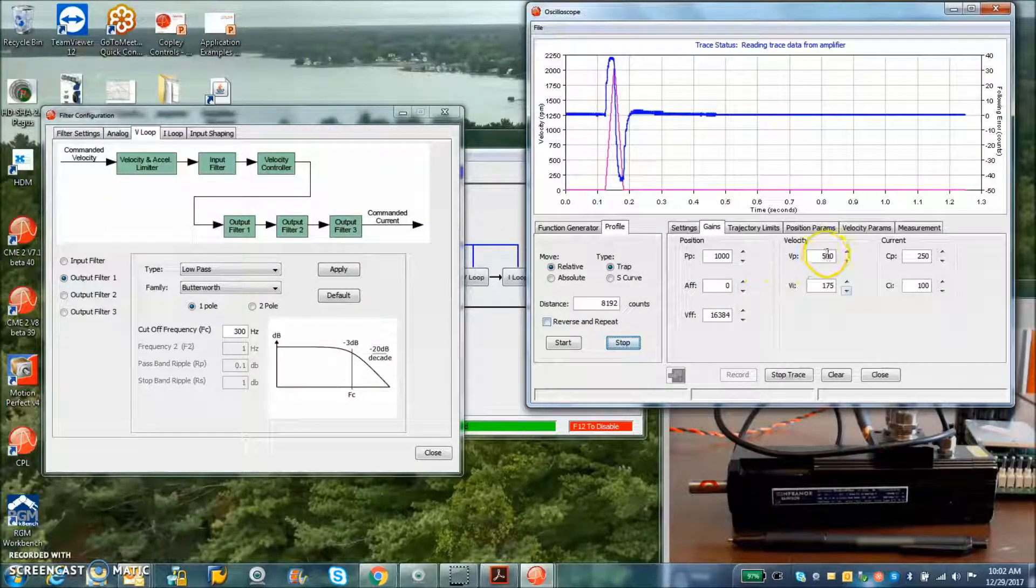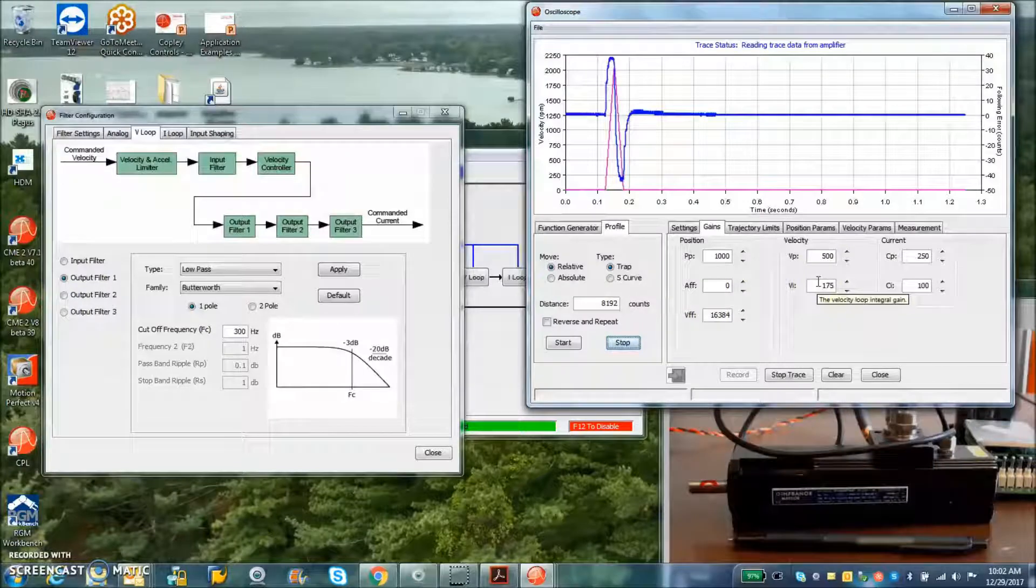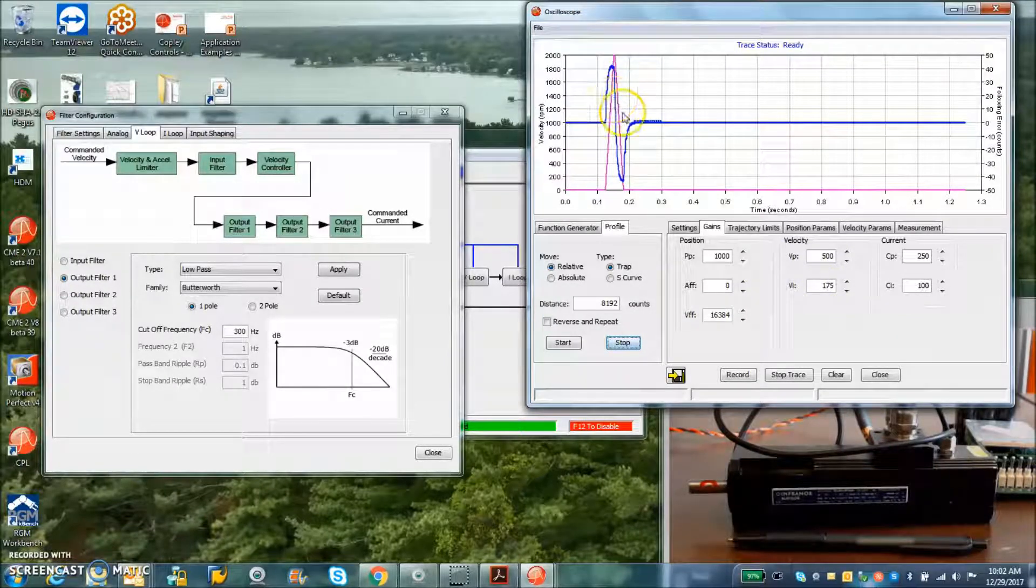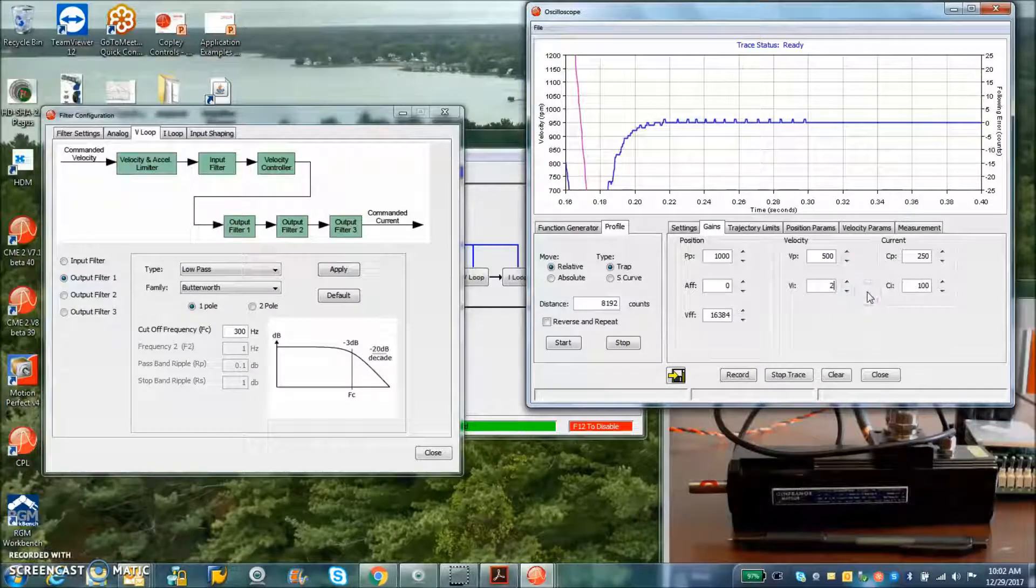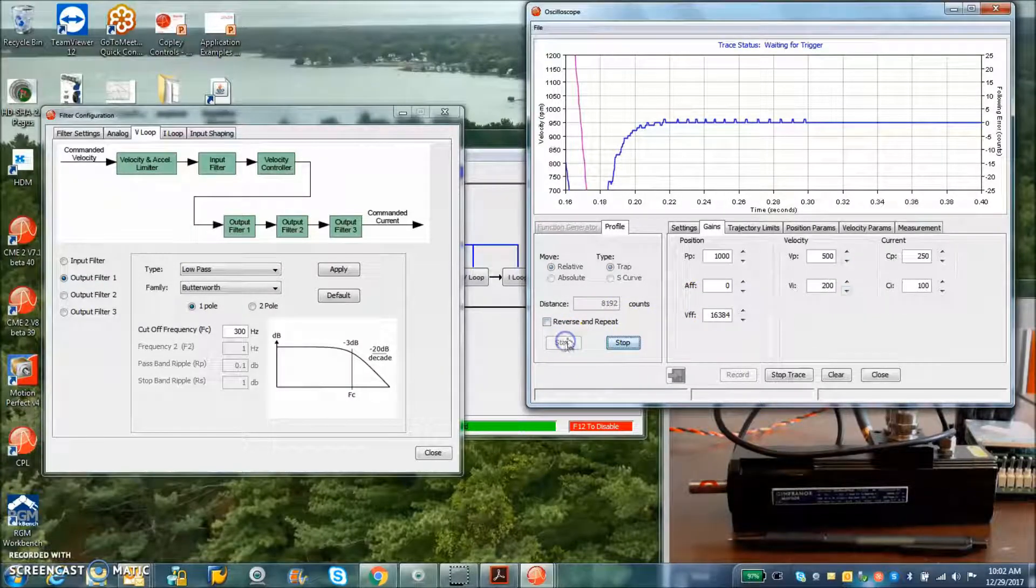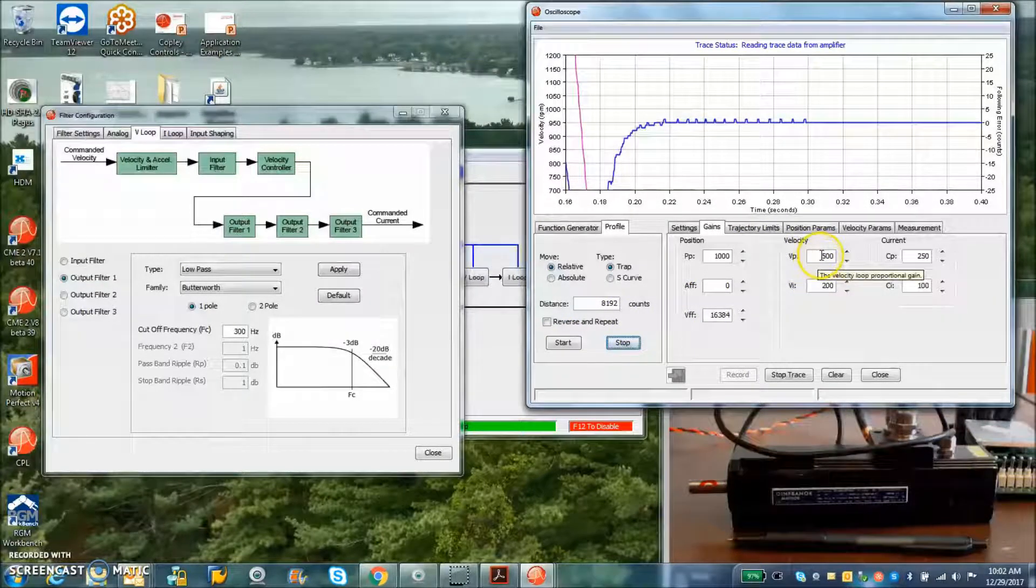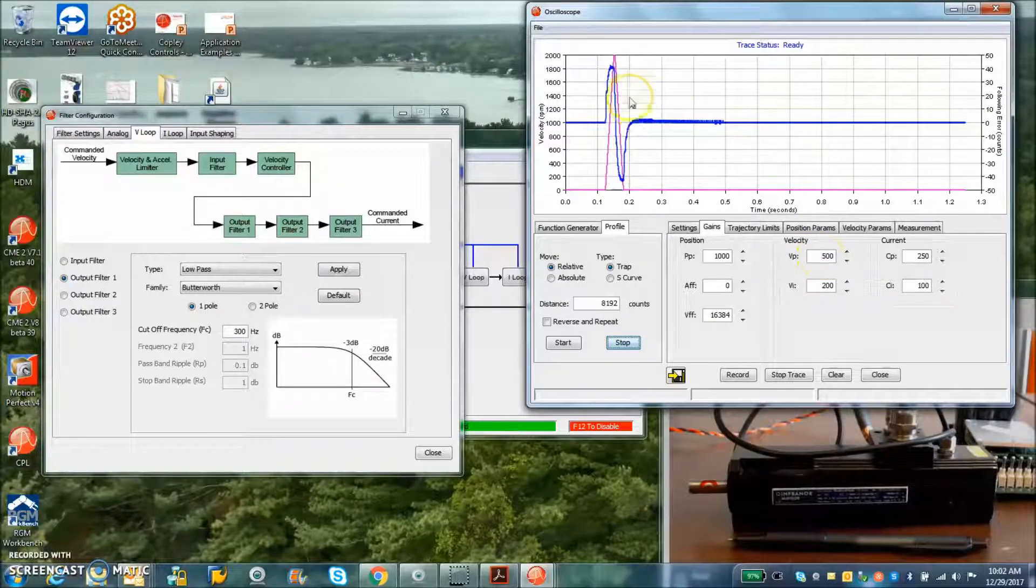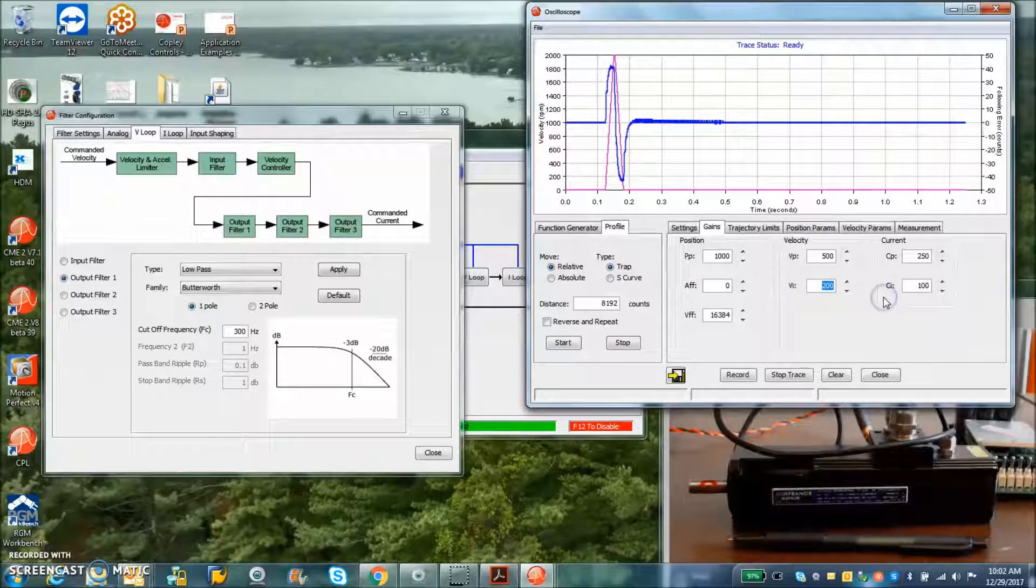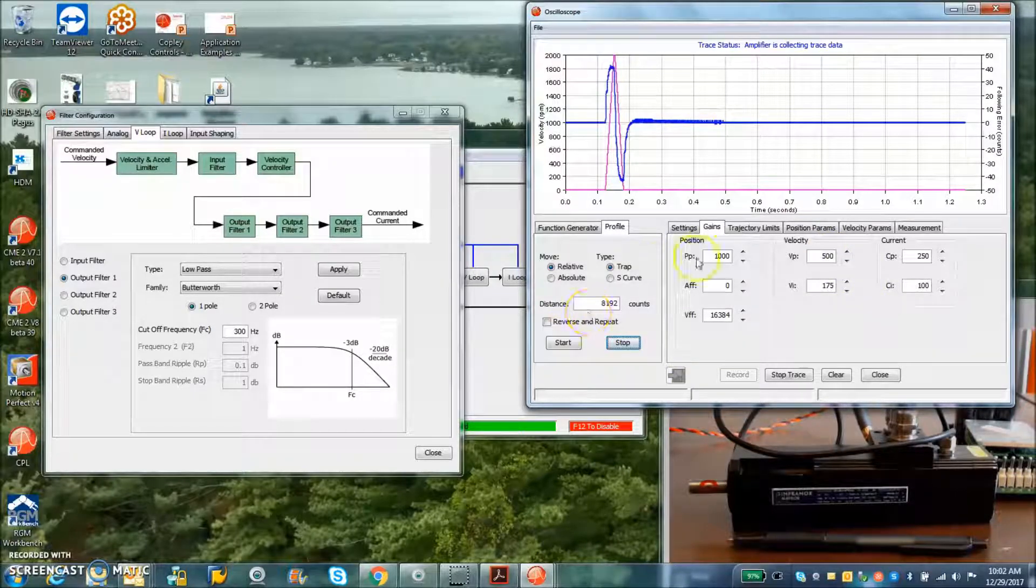So once we land on a value of VP and VI, we can bring them up and down together to increase the stiffness. You could loosen it up a little bit, make it not so ringy, just bring the VP and VI up and down together.